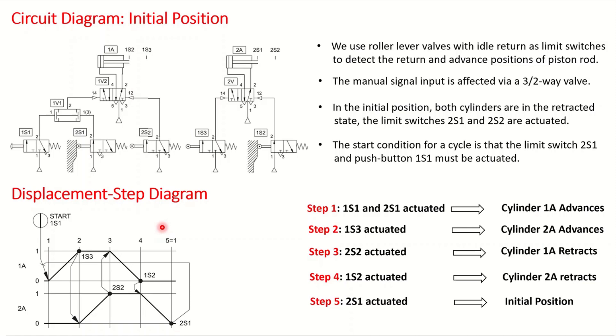Now that we have the displacement step diagram and know how to read it, let's look at the circuit we plan to design. The circuit has steps from 1 through 5, after which the system is ready for a new cycle. We have a directional control valve with a push button — when the operator presses it, the circuit is actuated. There is also a twin pressure valve already actuated, linking the second double-acting cylinder to confirm its retracted position before a new cycle can begin.